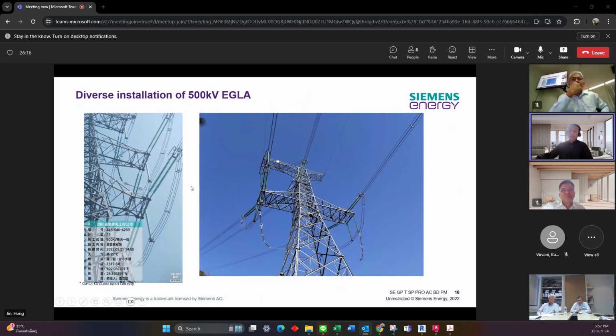For the other installation method, there are also many cases in China, because China has a big area, especially areas like Sichuan or Guangxi near Laos, and they have a very similar climate to Laos. Because they have many different types of tower, how do we make a standard design for the EGLA to fit all the different tower configurations? If you see, this is the configuration of the tension tower. They have tension insulators on both sides, and at the middle we have a jumper insulator. The customer wants to have one standard design to fit all different tower types.